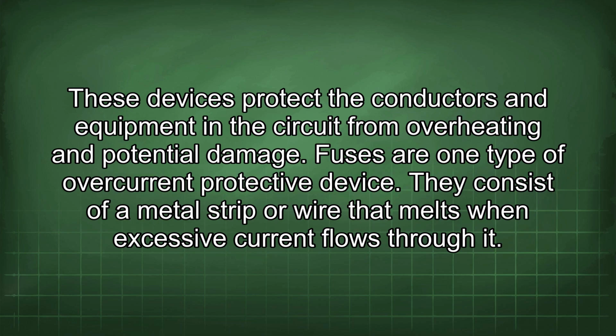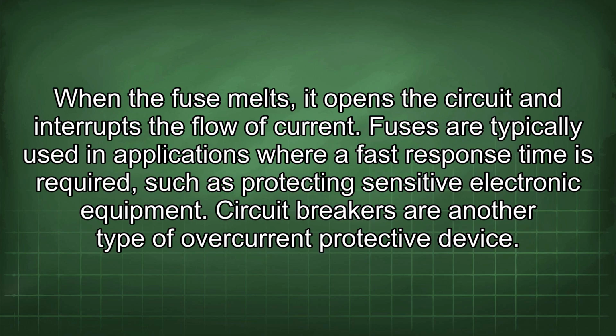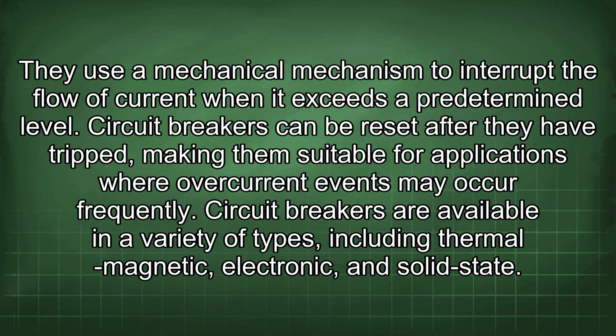Fuses are one type of overcurrent protective device. They consist of a metal strip or wire that melts when excessive current flows through it. When the fuse melts, it opens the circuit and interrupts the flow of current. Fuses are typically used in applications where a fast response time is required, such as protecting sensitive electronic equipment. Circuit breakers are another type of overcurrent protective device. They use a mechanical mechanism to interrupt the flow of current when it exceeds a predetermined level. Circuit breakers can be reset after they have tripped, making them suitable for applications where overcurrent events may occur frequently. Circuit breakers are available in a variety of types, including thermal, magnetic, electronic, and solid state.